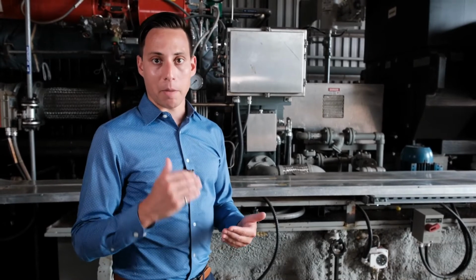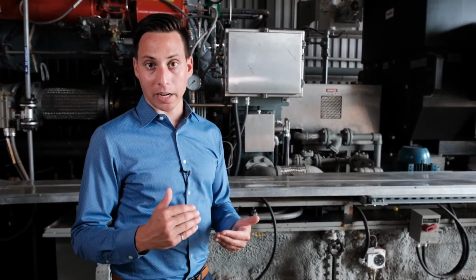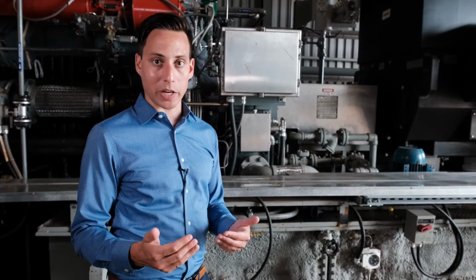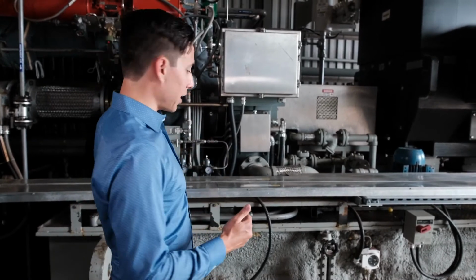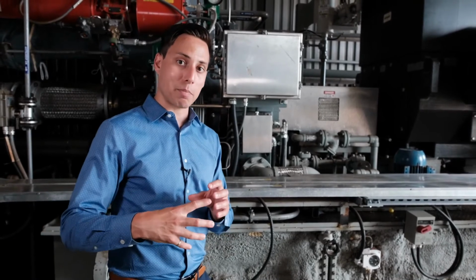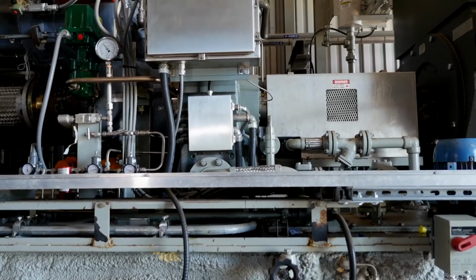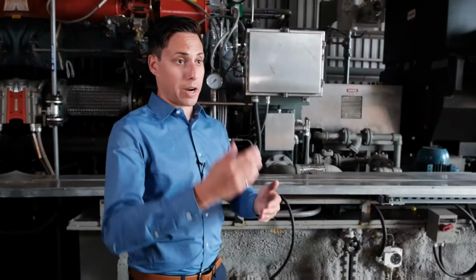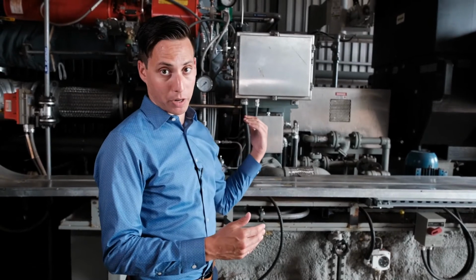Before it can provide the maximum amount of power possible to the second or low pressure stage, it must be reheated. So the air goes back outside to the thermal storage system, going through the low pressure heat exchanger, which injects the heat back into it, before coming out into the low pressure or second stage. From here, the air once again spins the low pressure impeller before being exhausted to the atmosphere.